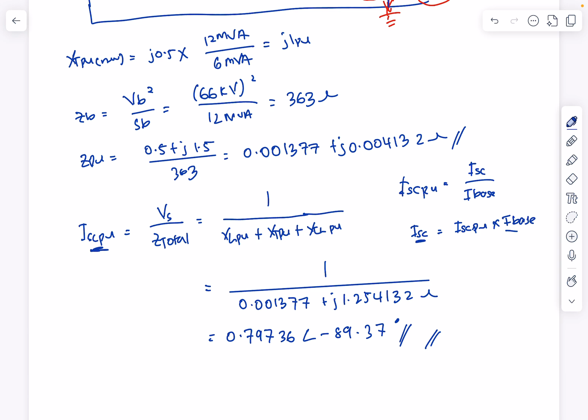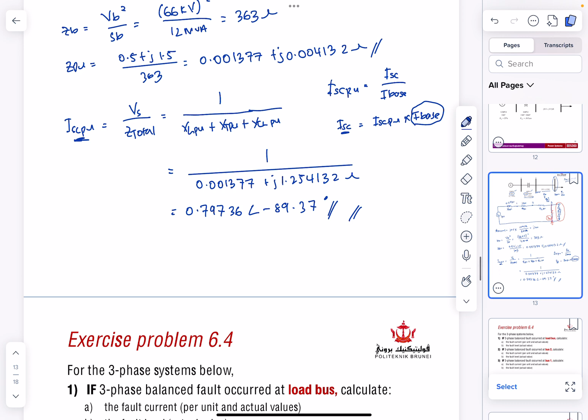So how do you calculate the actual values of this one? So I_SC per unit equal to I_SC divided dengan I base. So I_SC equal to I_SC per unit kali dengan I base. So if you want to calculate I_SC di sini, you need to know what is you punya I base. So I base di sini arah bus number 3, you can calculate by, as you recall in kamu punya per unit calculation, S_B equal to root 3 V_B I_B. Therefore, I_B equal to S_B divided dengan root 3 V_B.